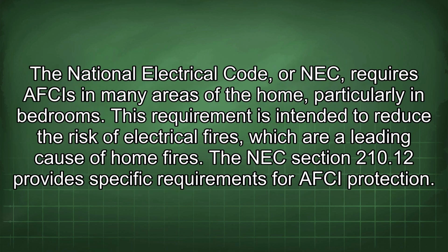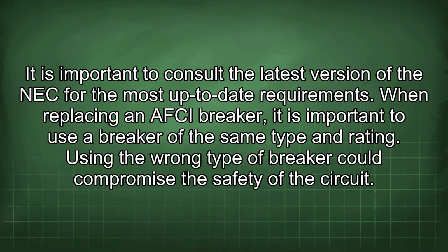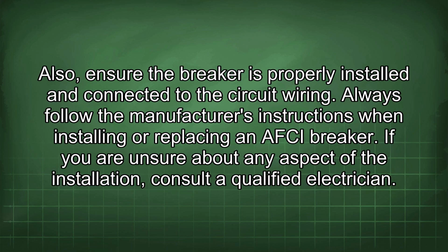The National Electrical Code, or NEC, requires AFCIs in many areas of the home, particularly in bedrooms. This requirement is intended to reduce the risk of electrical fires, which are a leading cause of home fires. The NEC Section 210.12 provides specific requirements for AFCI protection. It is important to consult the latest version of the NEC for the most up-to-date requirements. When replacing an AFCI breaker, it is important to use a breaker of the same type and rating. Using the wrong type of breaker could compromise the safety of the circuit. Also, ensure the breaker is properly installed and connected to the circuit wiring. Always follow the manufacturer's instructions when installing or replacing an AFCI breaker.